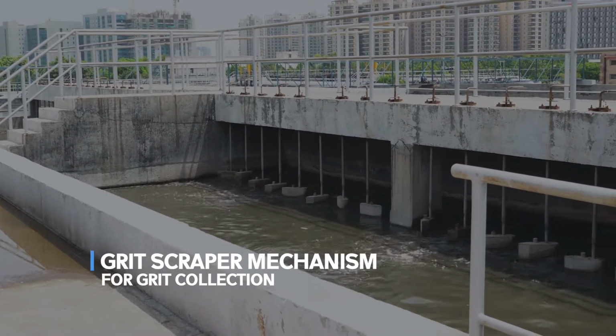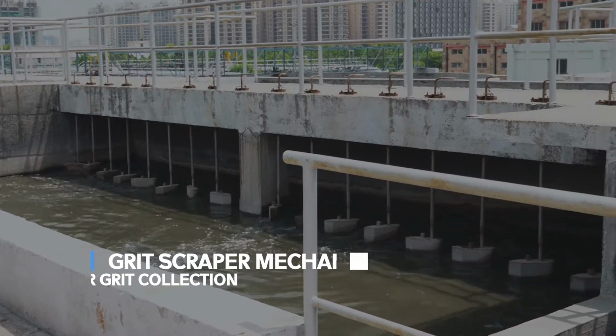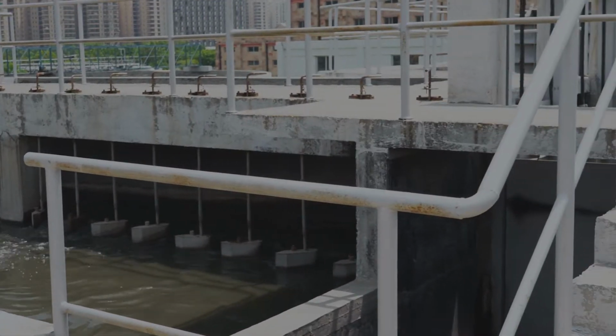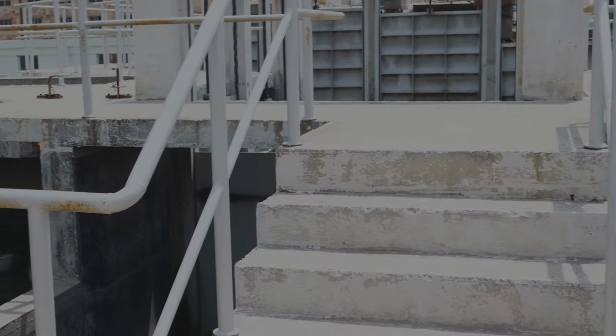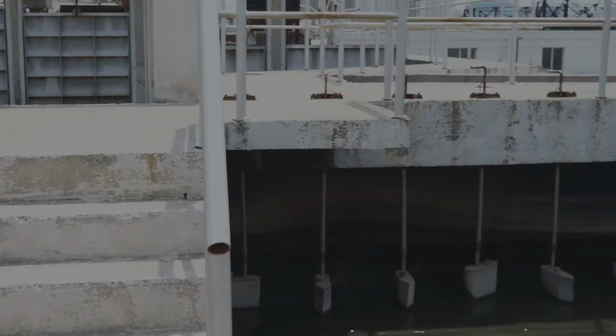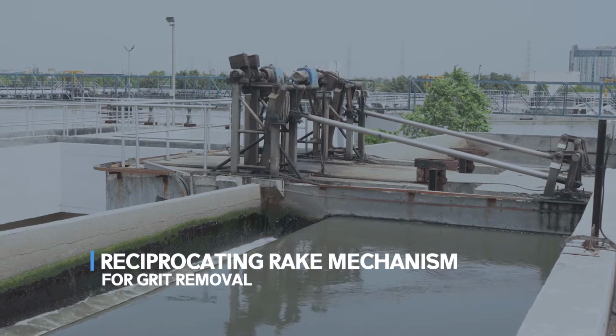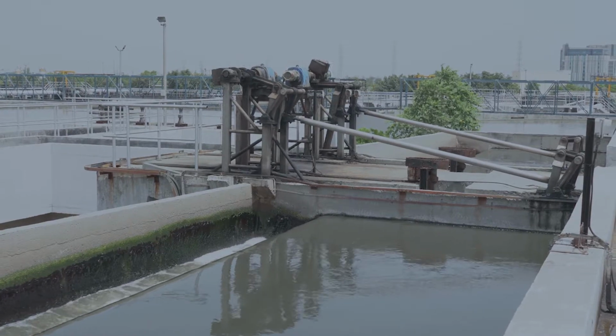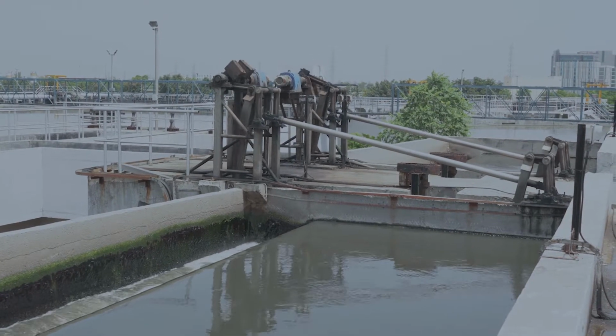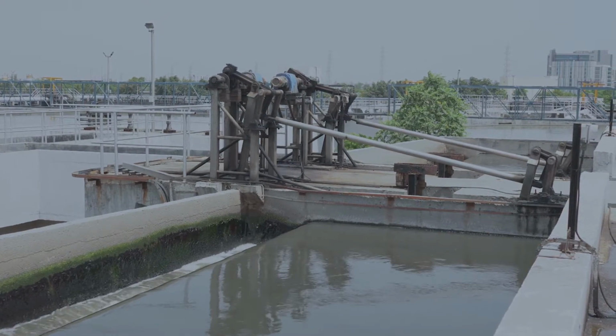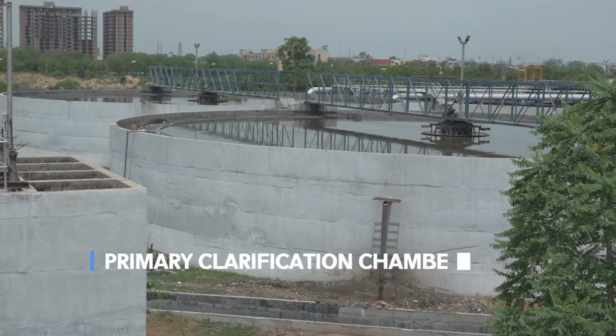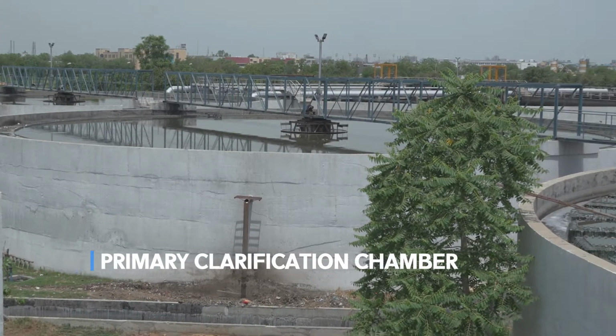After fine screening, the sewage flows to the grit separator chamber under gravity for separation of fine grit and inorganic particles. The grit chamber is constituted with a grit scraper mechanism for grit collection, a reciprocating rake mechanism for grit removal, and an organic return pump for recycling of organic matter into the grit chamber. The flow from the grit chamber is collected in the distribution chamber.